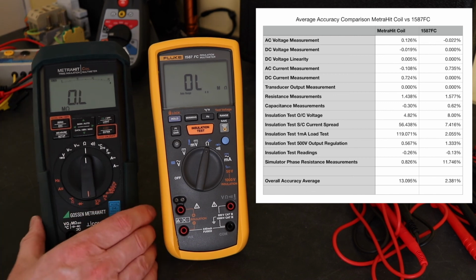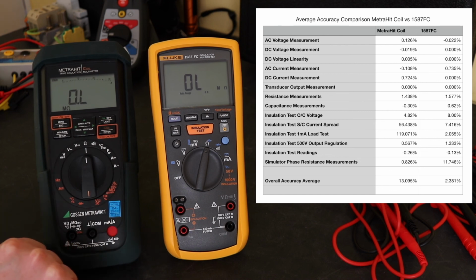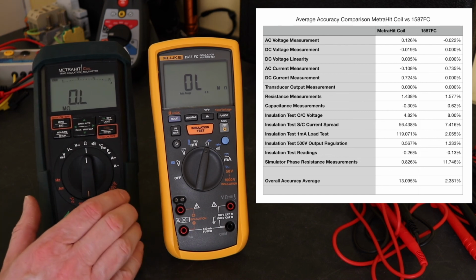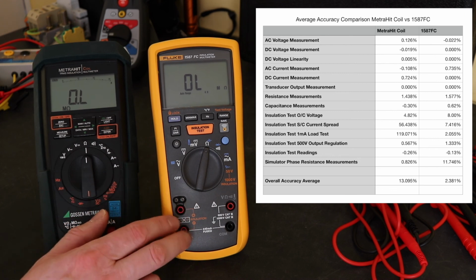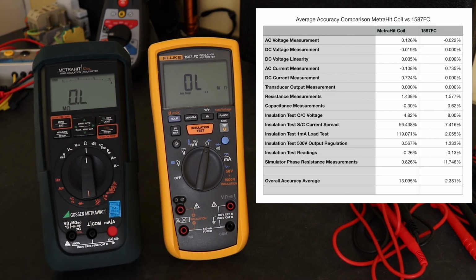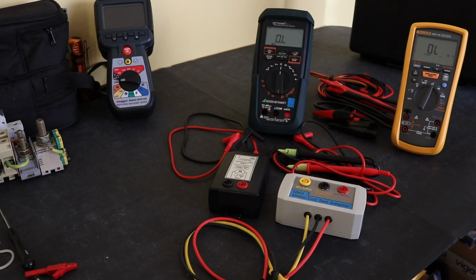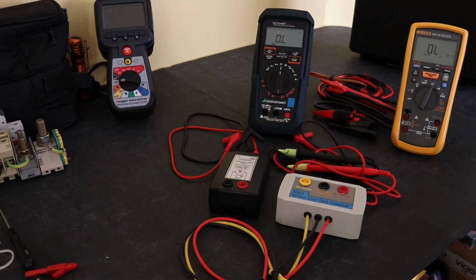So with those poor results on the current regulation of this unit, you actually end up with an overall accuracy of 13% for this one, just under 2.5 for the Fluke, so Fluke trumps it quite a bit there really. Okay, so decision time with these two instruments. So for me, unfortunately, with all the issues that I have surrounding the MetraHit Coil, with regard to how it does an insulation test, the lack of accessories that arrive with it, given the overall total cost, I find it very hard to justify purchasing that instrument over a Fluke 1587 FC.